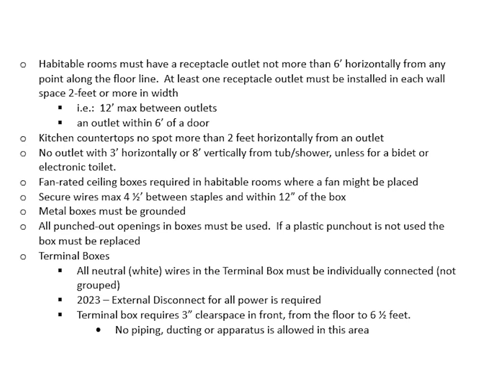Secure all in-wall wires with a maximum of 4.5 feet between staples and within 12 inches of the box. Metal boxes must be grounded. If you have multiple circuits coming into a single box, all of the grounds need to be tied together. All punched-out openings in boxes must be used. If a plastic punch-out has been opened and is not used, the box must be replaced. Terminal boxes require a 3-foot clear space in front, starting at the floor to 6.5 feet high. No piping, ducting, or apparatus is allowed in this area. And in the 2023 code, external disconnect for all power is required.